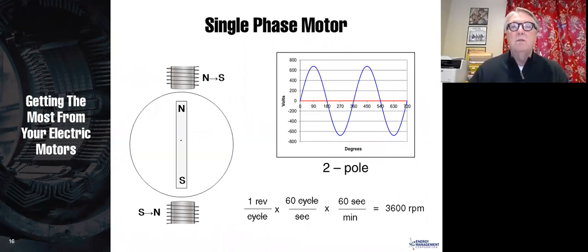Now I'm going to go back one slide because I want to talk about a single-phase motor. Single-phase motors have problems. Number one, you never know which direction they're going to go. Number two, they pulse, because when the voltage is very strong, then you have a very strong magnet. But when the voltage is 0, you have no magnet whatsoever. And so you get a pulsing magnet inside that motor that creates vibration inside the motor. So I liken this to a puppeteer who is trying to make the rotor go around, but all he can do is lift up and down. He can't go around. And you can do that, but somehow you have to get the thing started.